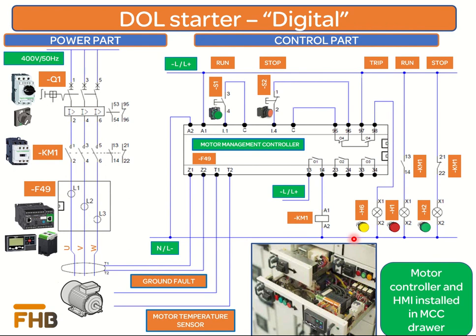As compared to conventional design, the motor controller provides additional protection features such as motor temperature monitoring, phase imbalance, phase failure, phase reversal, ground fault and locked rotor conditions. Like the conventional design, control voltage of the control scheme can either be an AC supply or a DC supply.